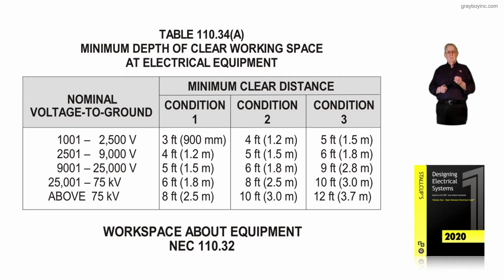Now, if we look at the next set of values, we pick up above 2,500 volts to 9,000 volts, and condition 1 is 4, 2 is 5, 3 is 6, etc. But notice we work around voltages today that are above maybe 9,001 up to 25,000 volts, like 13.8, 12,470, 13,200, 15 kV. And notice the clearances around such equipment for condition 1 is 5 foot, 6 foot, 9 foot, based upon the conditions. And then, of course, as the voltage goes up, the clearances in front of this equipment go up.